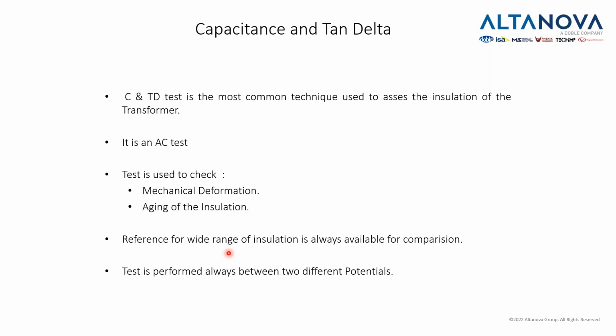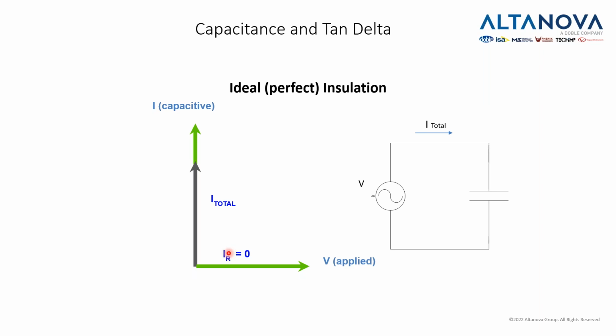And the good thing is that we can either evaluate the result using the standard, let's say, accepted values, or we can compare to results we obtained previously testing that transformer, or compare to some tests which have been executed in the factory when the transformer was produced.